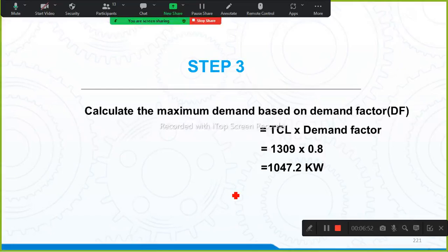Example, guys: when you go to a flat, in the kitchen we provide some 4 to 6 power sockets. Now, are we using these 4 to 6 power sockets 24/7? No, sir. All the power sockets will not be used 24/7. They are provided, but it doesn't mean that every socket has to be utilized 24/7. Maybe only one or 2 sockets may be used, or in the rooms we have a number of lights, which we are not using 24/7. We are going with AC also.